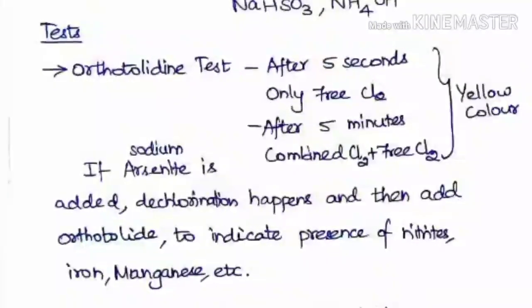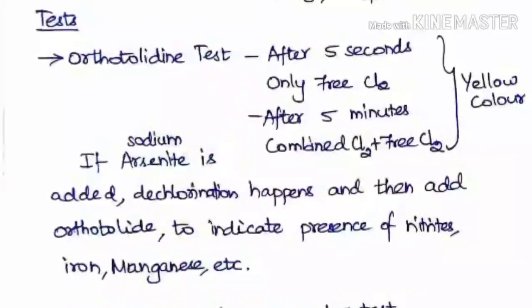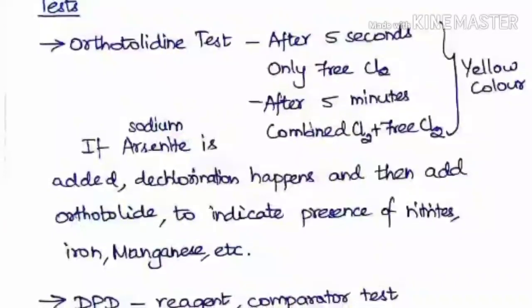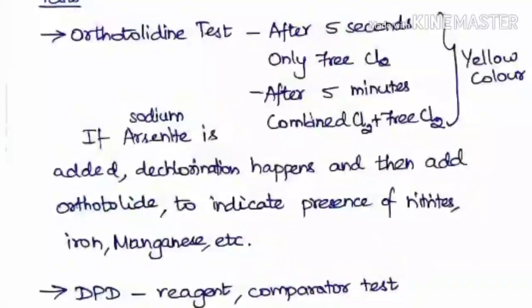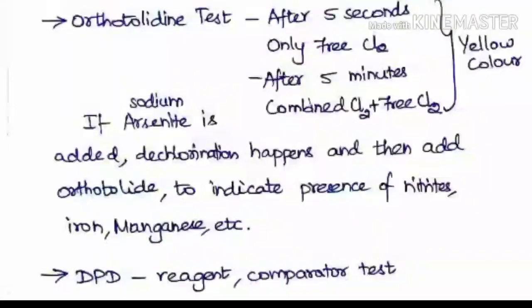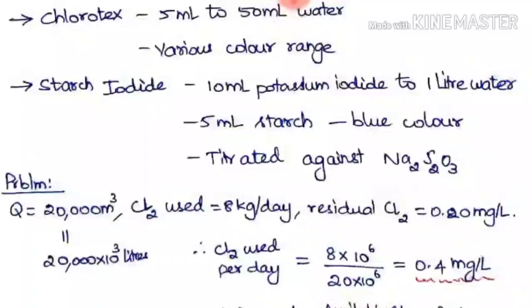The next is the DPD test. The DPD reagent is added to the water and similarly a red color blooms, which is compared with the standard solution to get the amount of chlorine present in the water. The next is the Chlorotex test. Chlorotex is a reagent used with water where nearly 5 mL of Chlorotex is added to 50 mL of water.